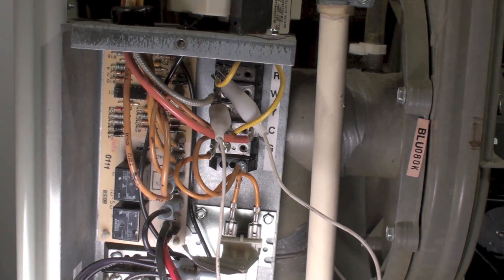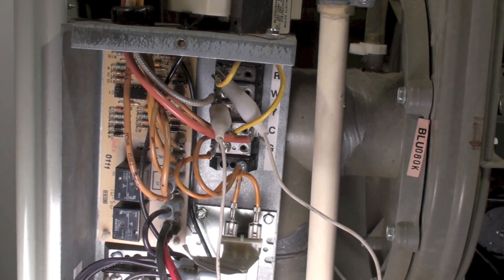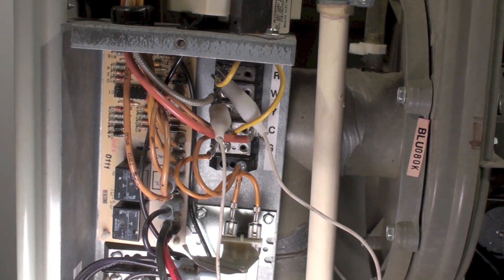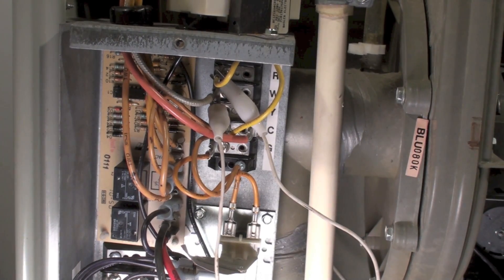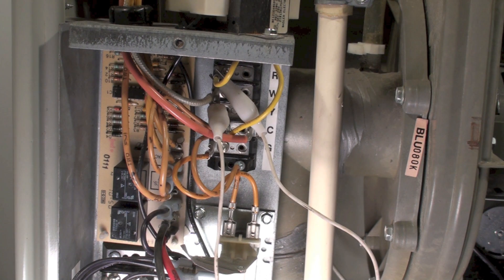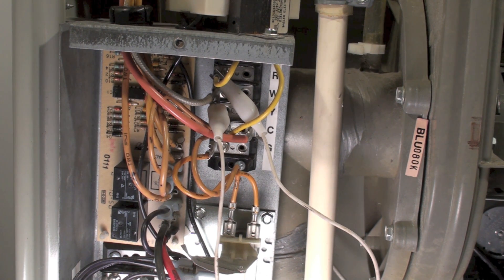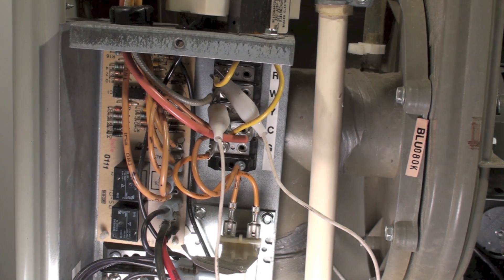First thing it's going to do is turn on the inducer. It's going to turn on now. And it's going to drop in its speed in just a sec. There it goes, drops the speed from high to low.